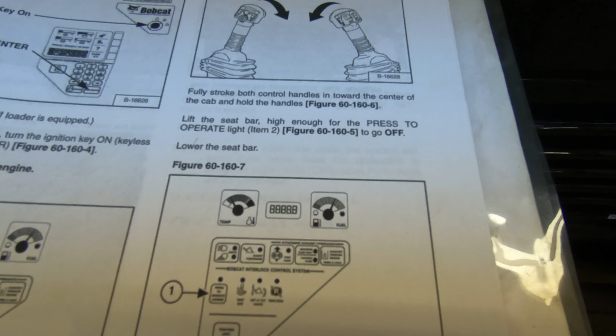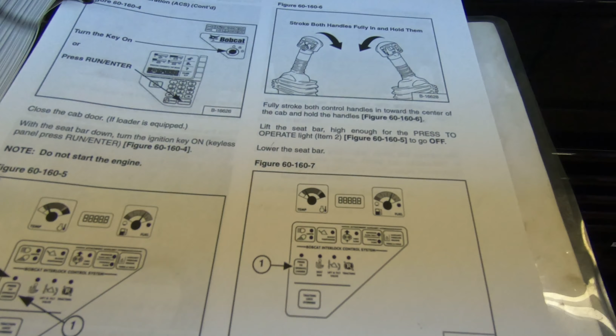Lift the seat bar high enough for the press to operate light to go off, which you probably have to have somebody else do for you, or kind of tie these together or something. I don't know how you're going to do that and do it at the same time. So press it for it to go off, or lift it so the light goes off, then lower the seat bar. Push the press to operate button to begin calibration.